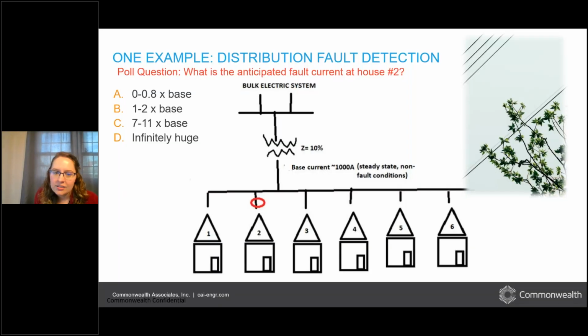So the correct answer in this case is that we would see roughly 10 times the current. So instead of our 1,000 amps flowing around that area, we might see something like 10,000 amps flowing in there. And that extra current is indirectly coming from those massive generation supplies that are up in that bulk electric system area of our screen. But things are limited by the design of our transformer. So we won't see infinitely huge fault current, but we might see something around 10,000 amps flowing into that red circle. This is a line to ground fault, very common on the power grid.